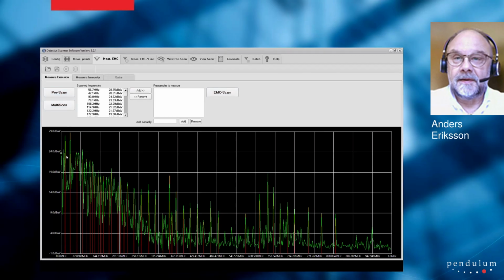It will only result in this trace from the spectrum analyzer, this graph, and this list of peaks. And what we do is put the spectrum analyzer in max hold mode, and then we just scan the board, and amplitudes will accumulate on the spectrum analyzer, and then we just dump it into the software. So this will not tell you exactly where on the board you have peaks or sources, but it will tell you the worst case on the board.